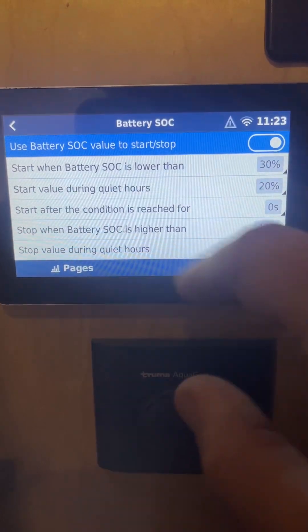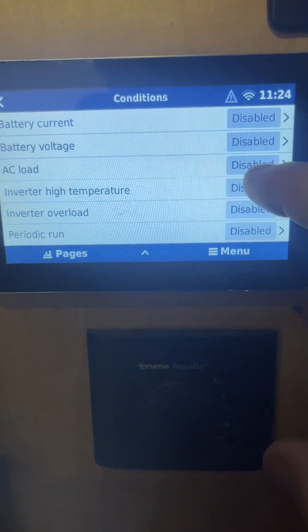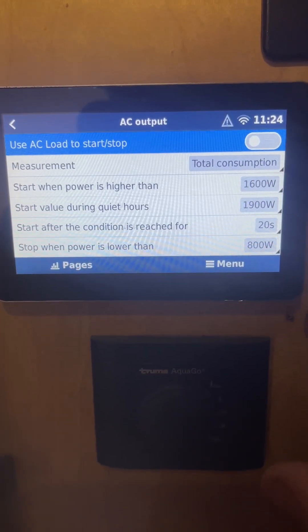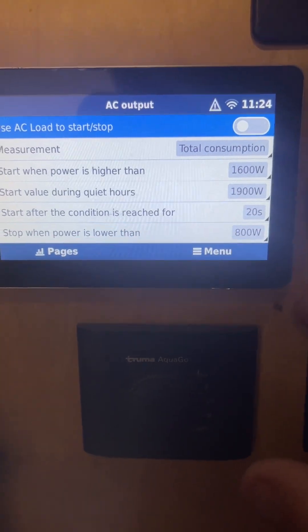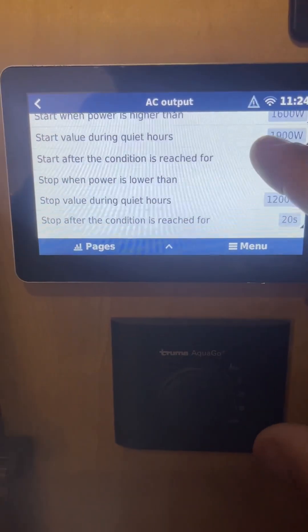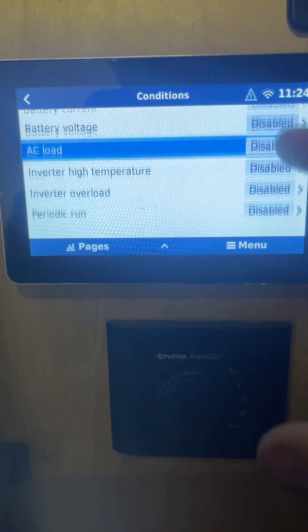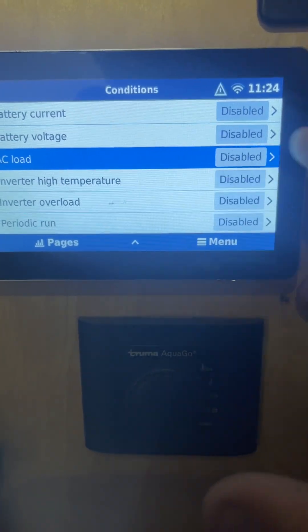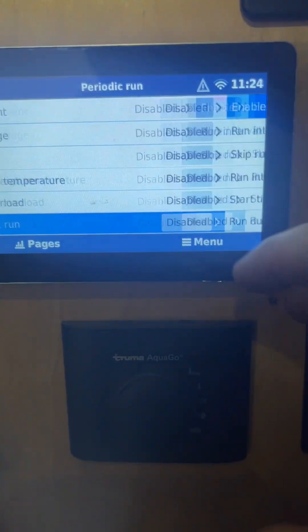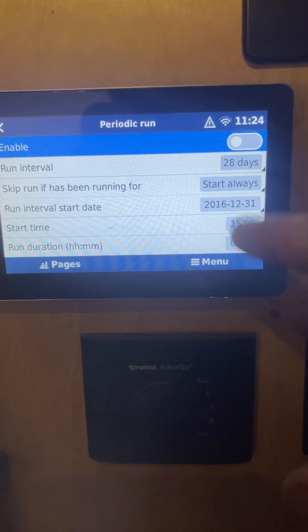You can also trigger the generator based on other conditions, like battery voltage, or your AC loads — for example, if you're running more than 2,000 watts at once, it'll just keep the generator on. You can also set it to turn on if the inverter gets hot, if the inverter gets overloaded, or set it to periodically run every so often just to keep the generator exercised.